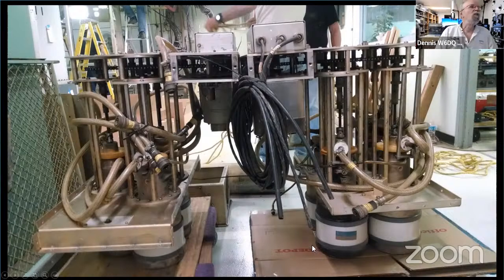When Collins first built this transmitter and installed it, they were not water cooled. These are Jennings vacuum variable capacitors, if you're familiar with those. What they found is these capacitors would get extremely hot and fail - they had a real high failure rate. So Collins went back to Jennings and said, we need to do something different, and they came up with this design of a water-cooled vacuum variable. Who ever heard of a water-cooled capacitor? That was a new one on me. Water and high voltage, I don't know - those two things don't really mix very well.